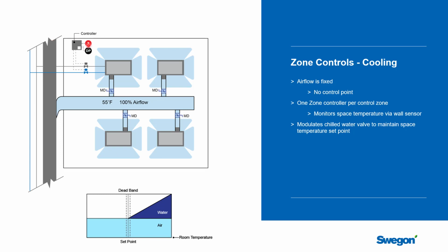Now, once you have a control zone, you'll have one controller in that control zone, and it will treat all the beams the same. And so it will be monitoring the conditions in that space. We're going to talk through these different sequences shortly, but it will be gathering data about that space and making decisions. And whatever decision it makes, it will get all the beams that service that zone to behave the same. So we have our primary air main duct here. You can see we're branching off. It's typically around 55 degrees, although it can be warmer. That's not a right or a wrong. And because this is a constant volume system, you're going to get design airflow rate all the time. And you can have manual balancing dampers in here to make sure that each beam gets the right amount of air.